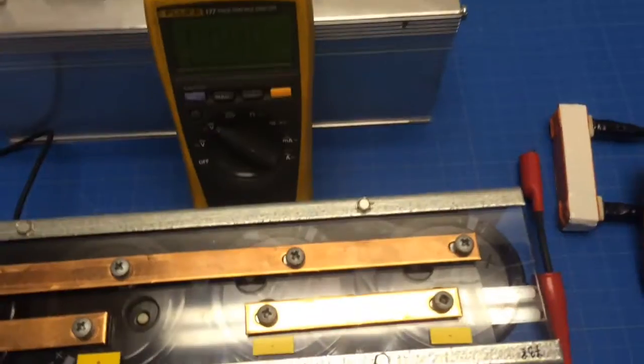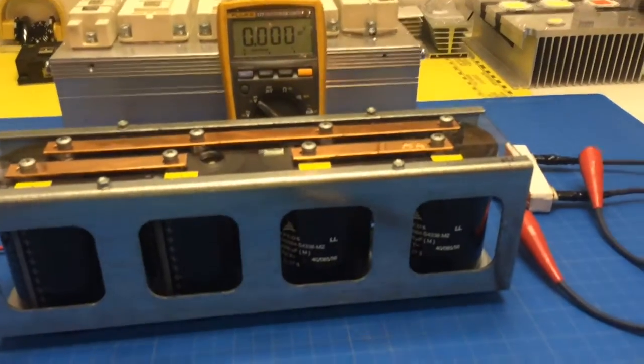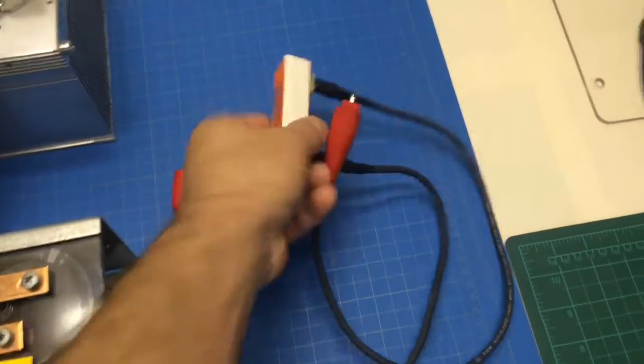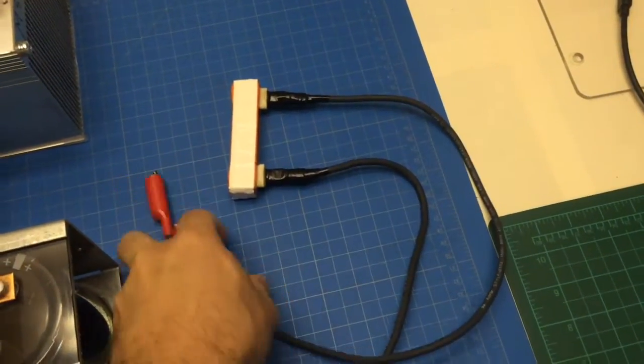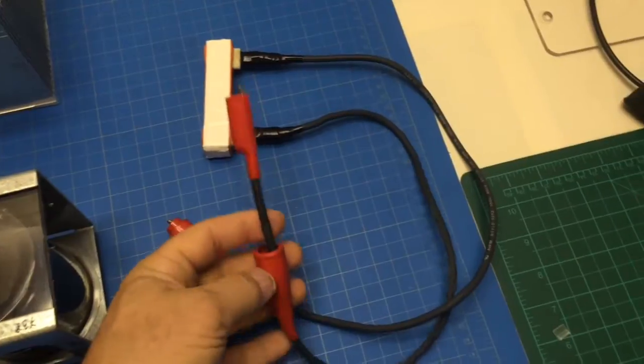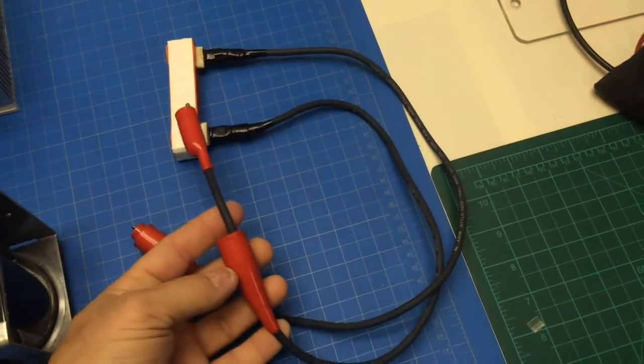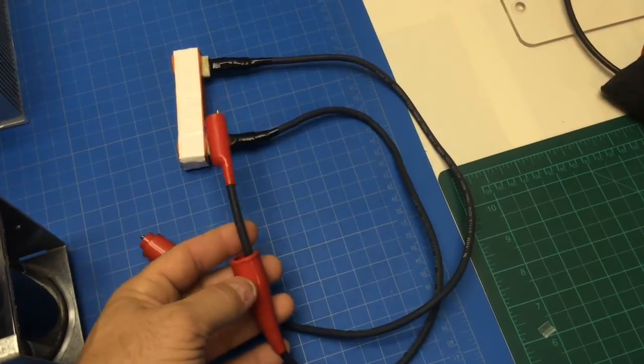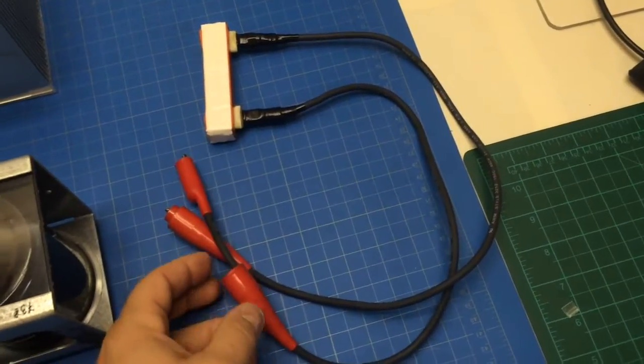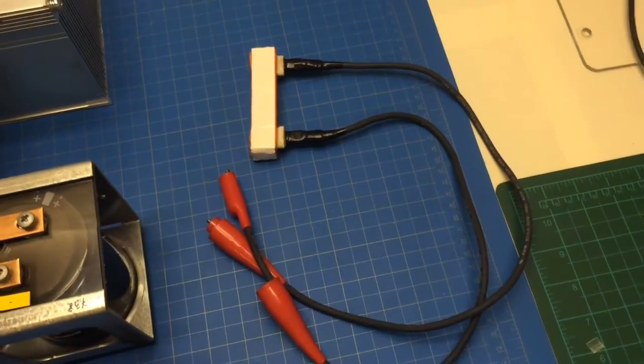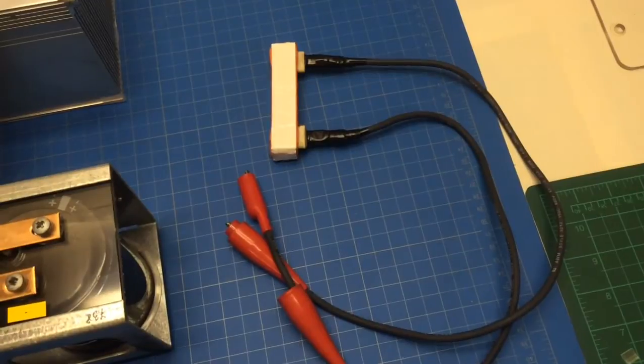Here's a small capacitor bank that's been sitting here with a charge on it for a little while. We're going to take this high wattage resistor to discharge that capacitor bank. This was built for large capacitor banks around 700 volts. Once the power's de-energized, it takes a little while for the bleeder resistors to drain it down. I don't completely trust them.